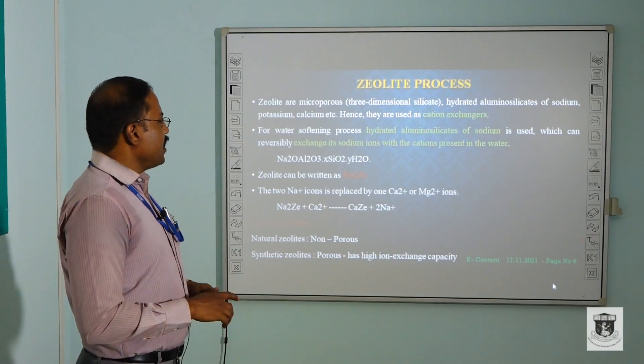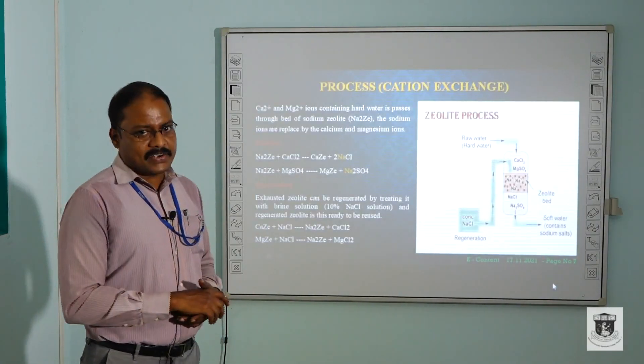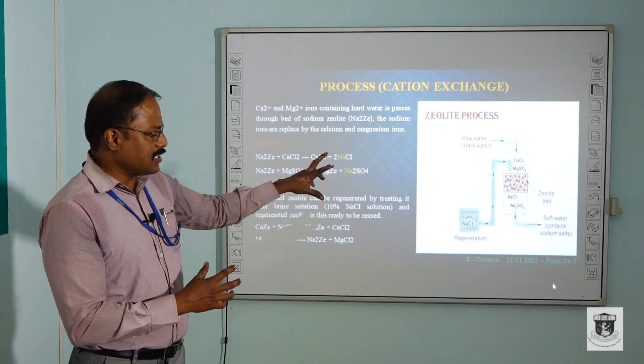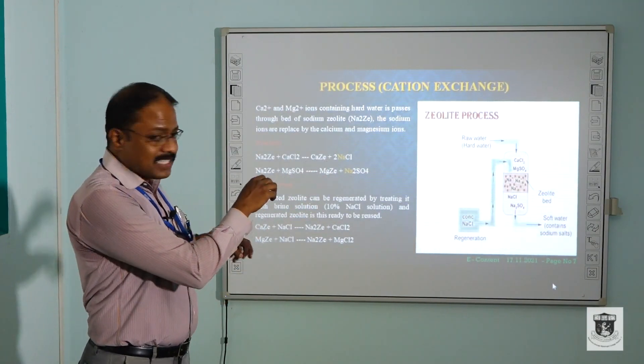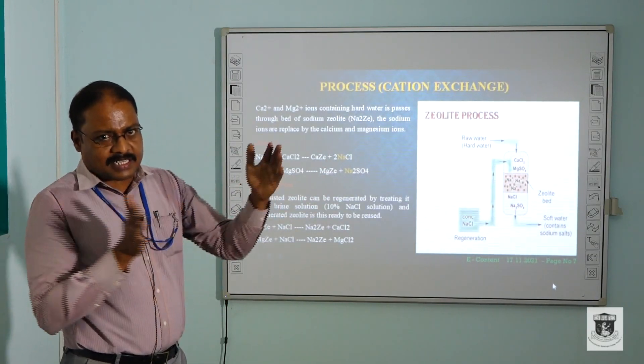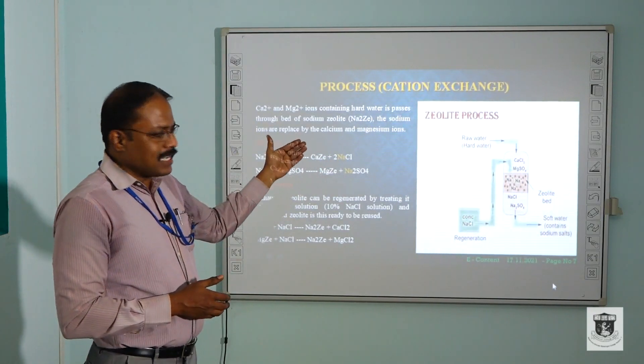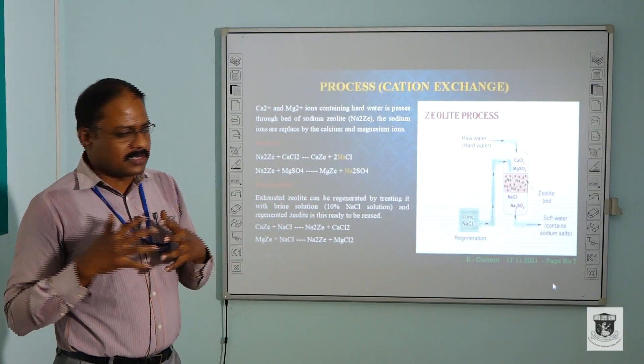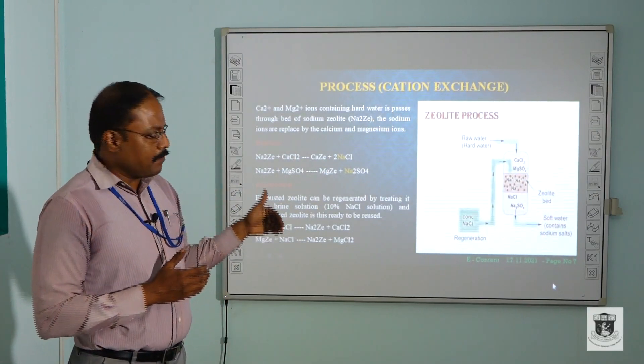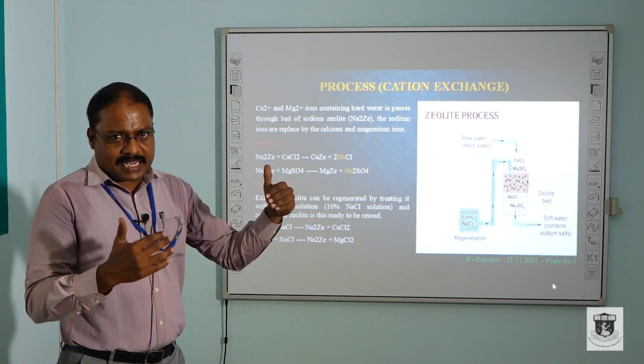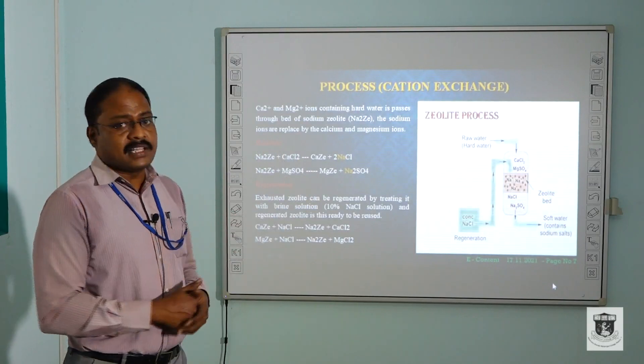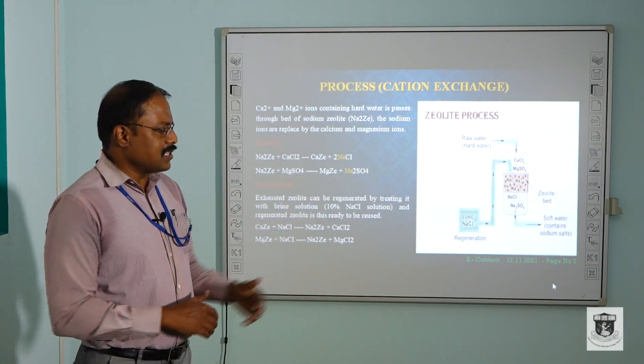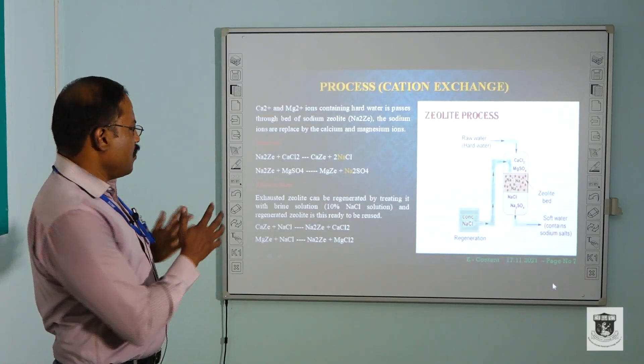Now we look at the process — the schematic diagram of the zeolite process. We have a cylinder with a bed containing Na₂Ze, the sodium zeolite. We pass the raw hard water, which contains calcium and magnesium ions, through this bed. The cation exchange bed replaces the cations from the hard water. Finally, you get sodium replacement ions — sodium chloride, sodium sulphate — and the soft water containing sodium salts comes out below.